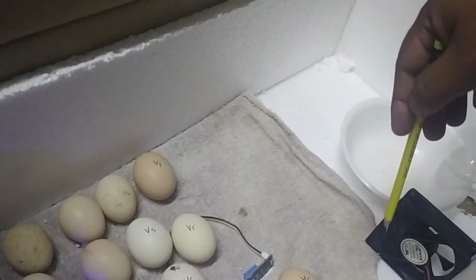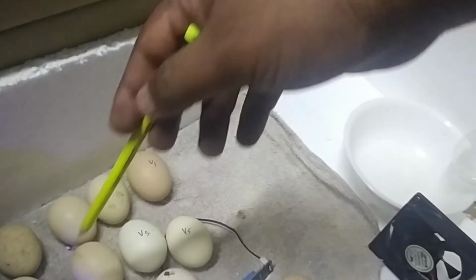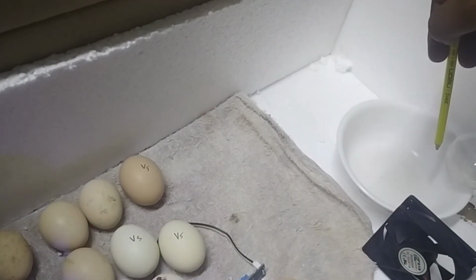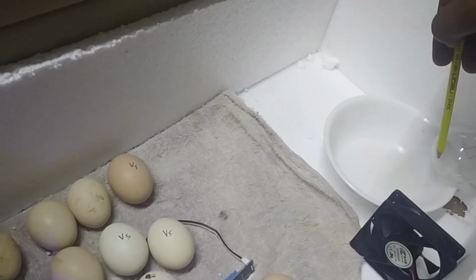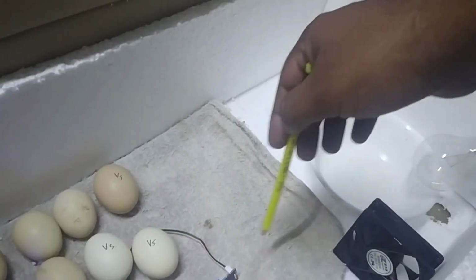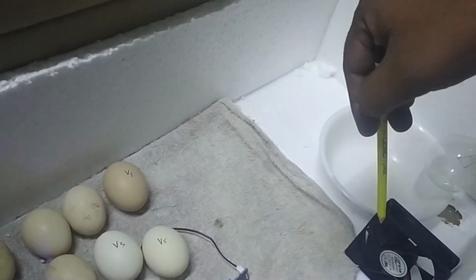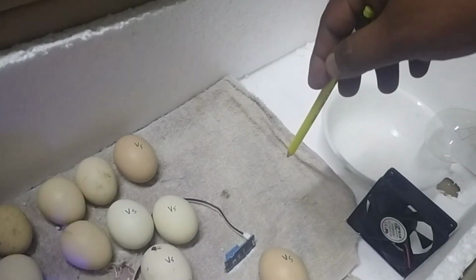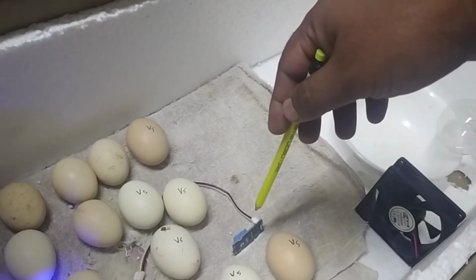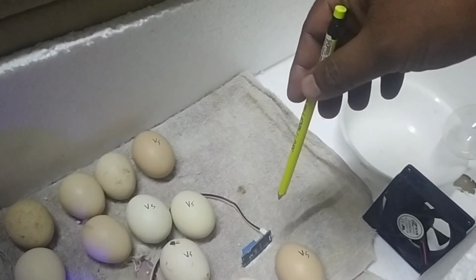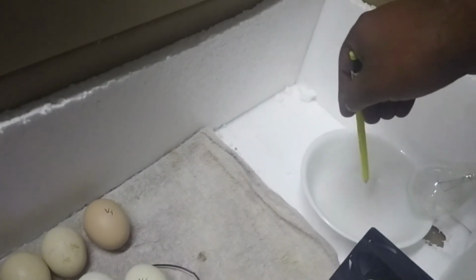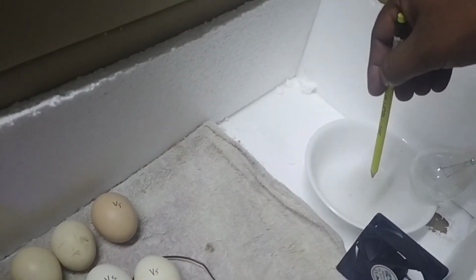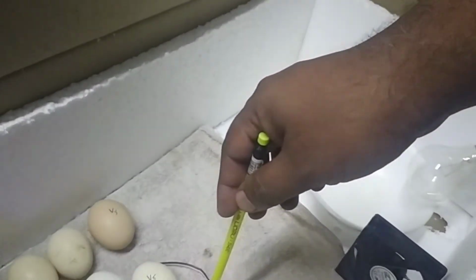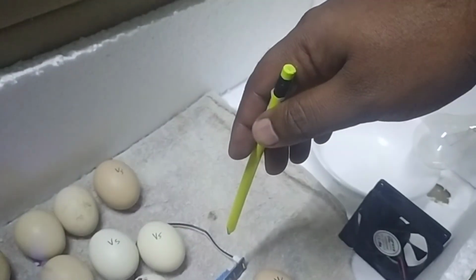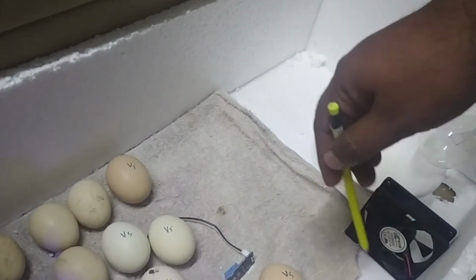And in air, convection has the maximum effect. So there is no convection, and due to that there is a temperature gradient. There's a temperature difference between the bulb and the sensor, and that's why this recorded a higher temperature than this. However, when this fan was turned on, there was convection and the temperature remained the same throughout. The other effect that we saw was the humidity had decreased. The reason for humidity decrease is because the humid air from here does not get circulated to the rest of the eggs. So the humidity at rest of the incubator will drop if the fan is turned off.